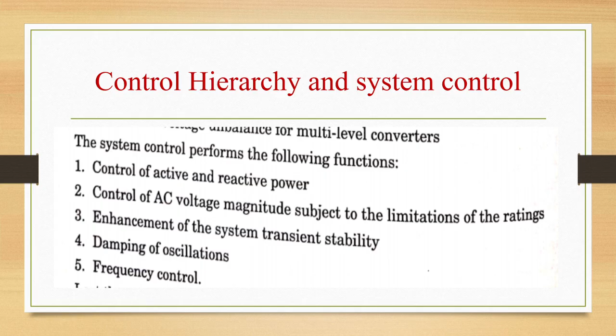System control will perform the following functions. First one is control of active and reactive power. Second is control of AC voltage magnitude subject to the limitations of the ratings. Third is enhancement of the system transient stability. Fourth is damping of oscillations. Fifth is frequency control. Last three functions require modulation of the active power based on appropriate control signals and control laws. In performing these functions, there is no significant difference between LCC and VSC based HVDC links except for the differences due to their individual characteristics.